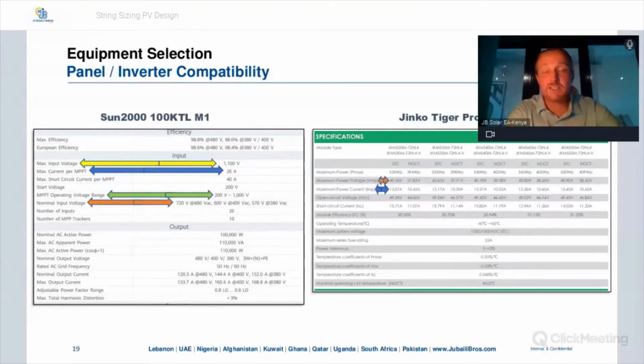So remember, this is max current per MPPT. Each MPPT accepts 2 strings. So you probably should not connect 2 strings to the same MPPT if the max power current is 15, because then it would require 30 amperes in that MPPT. So that's fine, you would just connect one string to that MPPT. You will not connect two strings. So I'll make that a little bit more clear in a few slides.